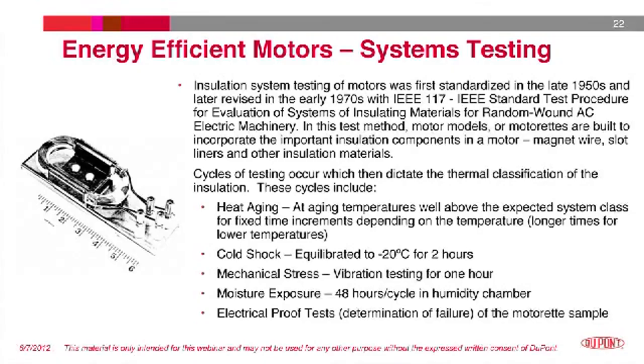Testing of complete insulation systems was first developed in the late 50s and revised in the early 70s. The first standard test method developed was IEEE 117, IEEE Standard Test Procedure for Evaluation of Systems of Insulating Materials for Random Wound AC Electric Machinery. In this standard test, motorettes are built that model the important components of the motor, magnet wire, slot liners, etc., and enable a thermal evaluation of these materials to determine life characteristics. Cycles of thermal aging followed by cold shock, mechanical stress, moisture exposure, and then electrical proof tests simulate motor operation, and the failure of the proof test determines the life limits of the system. For motors whose primary failure was thermal, this proved to be a useful tool and has been broadly used for 50 years.